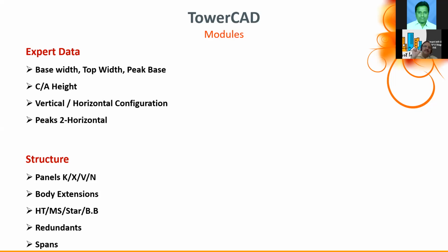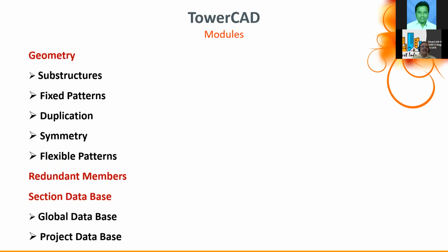This includes the top width, peak base, cross arm height, and vertical and horizontal configuration. For 400 kV we consider 2 peaks, meaning 2 earth wires. The panels in the tower have K-type, X-type, V-type, and N-type bracings. Body extensions use high tensile steel, mild steel, and built-up sections like star angles and back-to-back angles, and we also use 4-angle members, along with redundants and spans. So this is the geometry of the substructures.